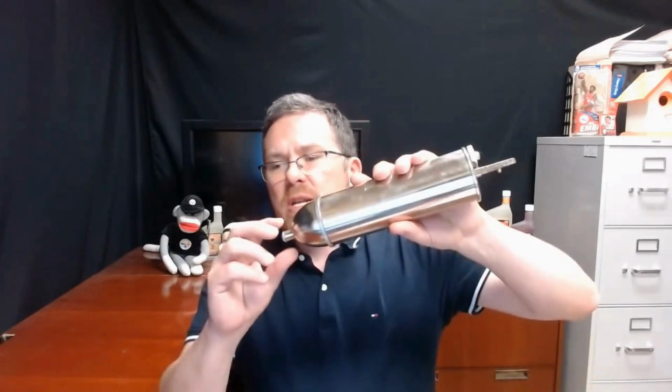There is, however, an easier way even than that to do it, and that is to have a bacon bomb that actually has attachments that screw into the end. Now, one of the ones that, let's say, Bell Performance has, it has specially designed attachments that are of differing lengths. It has a 3-inch attachment, a 6-inch attachment, and a 12-inch attachment. And so let's say you need to do a sample 6 inches off the bottom. You would take the 6-inch attachment and you would screw it into the bottom. And then when you lower it down, when it hits the bottom, it's at 6 inches. It's at exactly the right height that you need it to be at. And so you're going to get good consistency with your results. Okay, so that's the best way to take a sample.